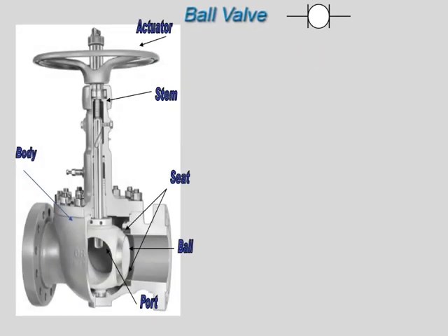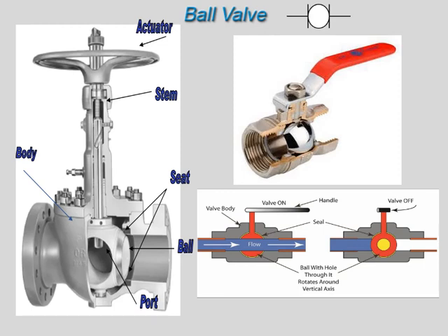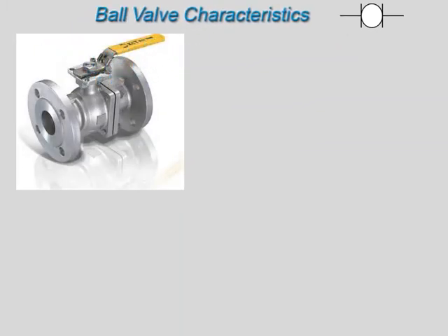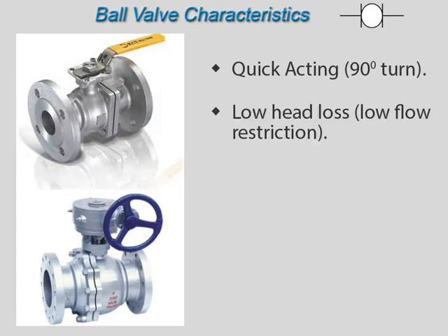A ball valve is a rotational motion valve that uses a ball-shaped disc to start, stop, or throttle fluid flow. The valve is opened by aligning the ball port with the valve body inlet and outlet. The valve is fully closed when the ball is rotated 90 degrees so that the port is perpendicular to the flow openings of the valve body. Most ball valve actuators are the quick-acting type, requiring only a 90-degree turn of the handle to operate the valve. For large ball valves, the ball can be difficult to turn and may have actuators with mechanical assistance. The main advantages are quick-acting quarter-turn on-off operation, very little flow restriction when open, and positive flow isolation with low torque. The main disadvantage is that conventional ball valves have relatively poor throttling characteristics.